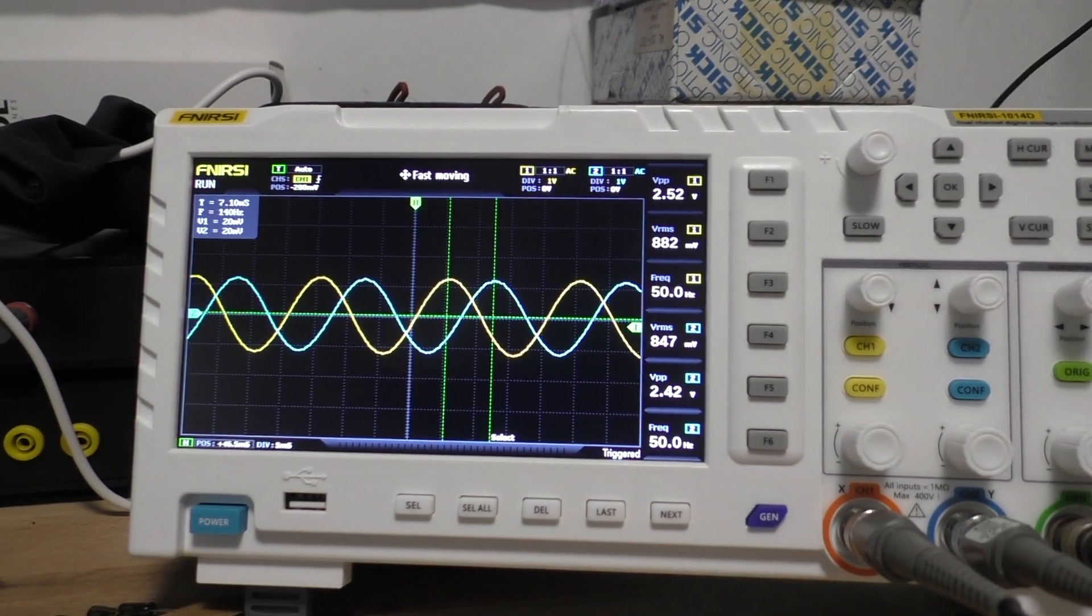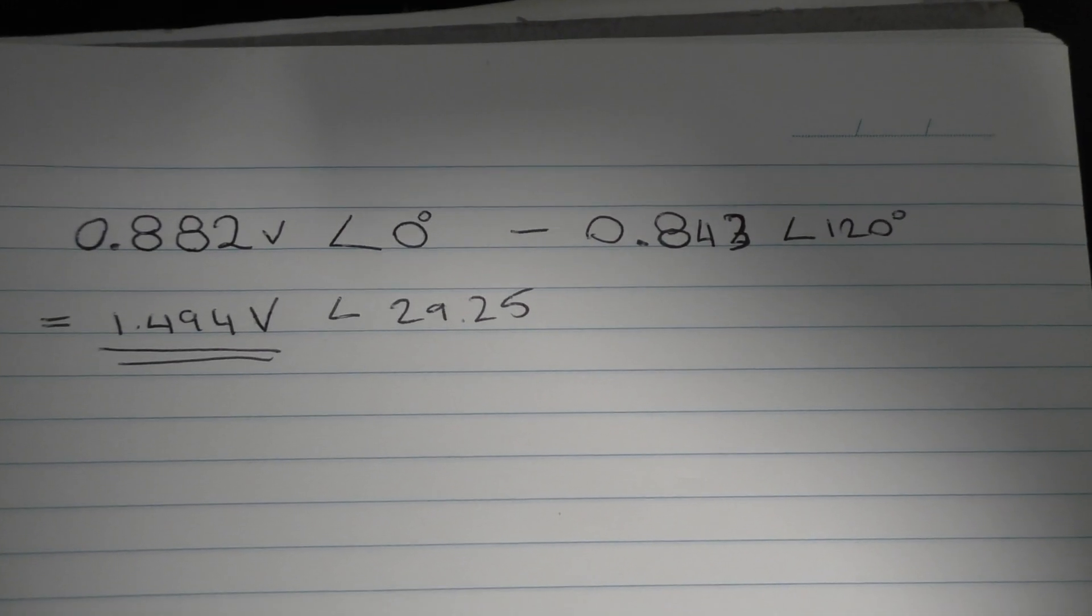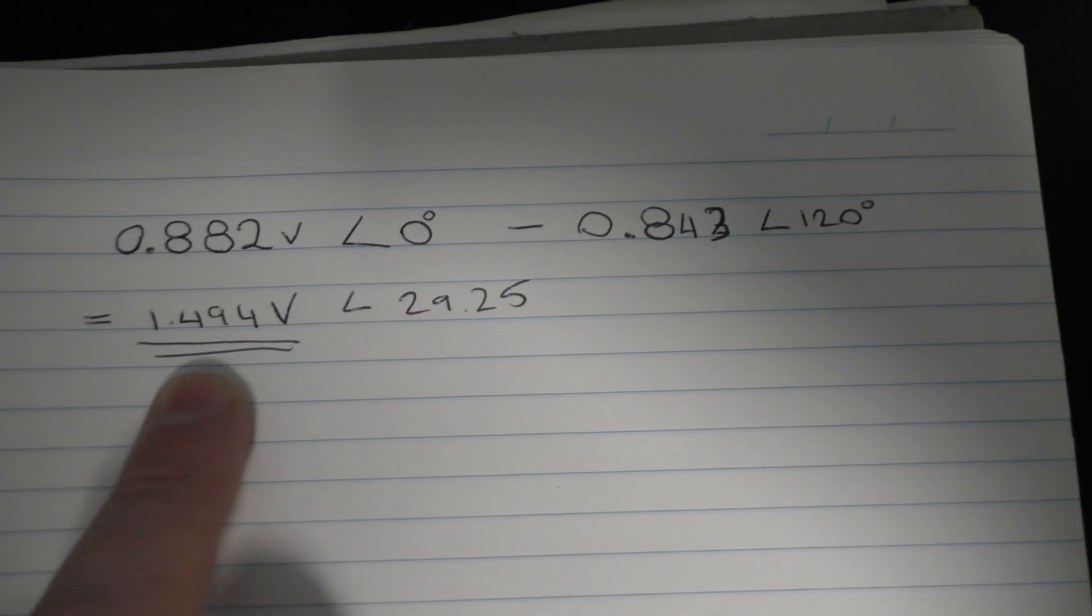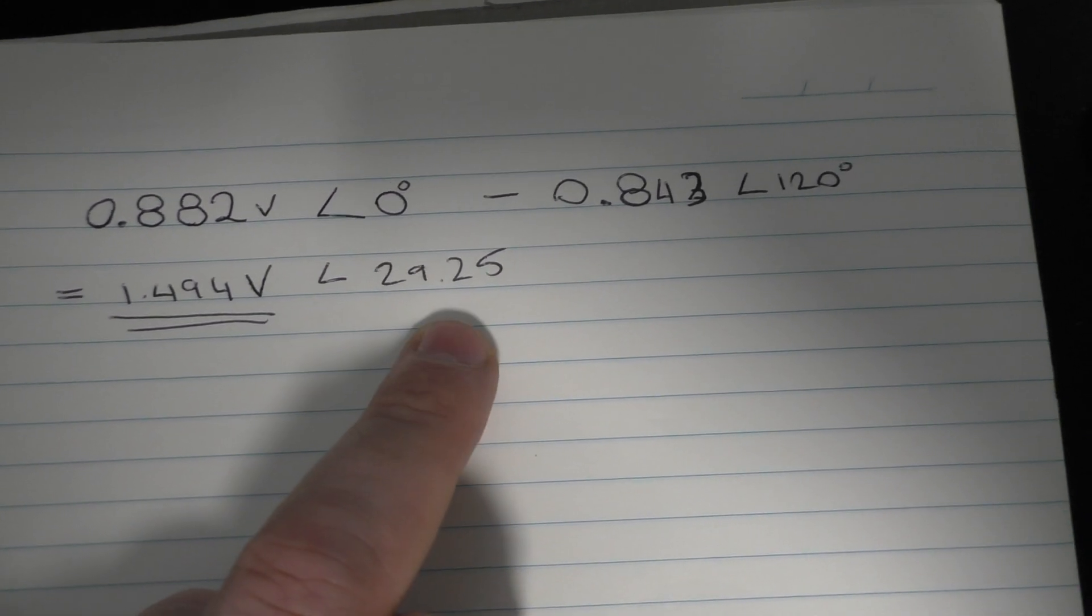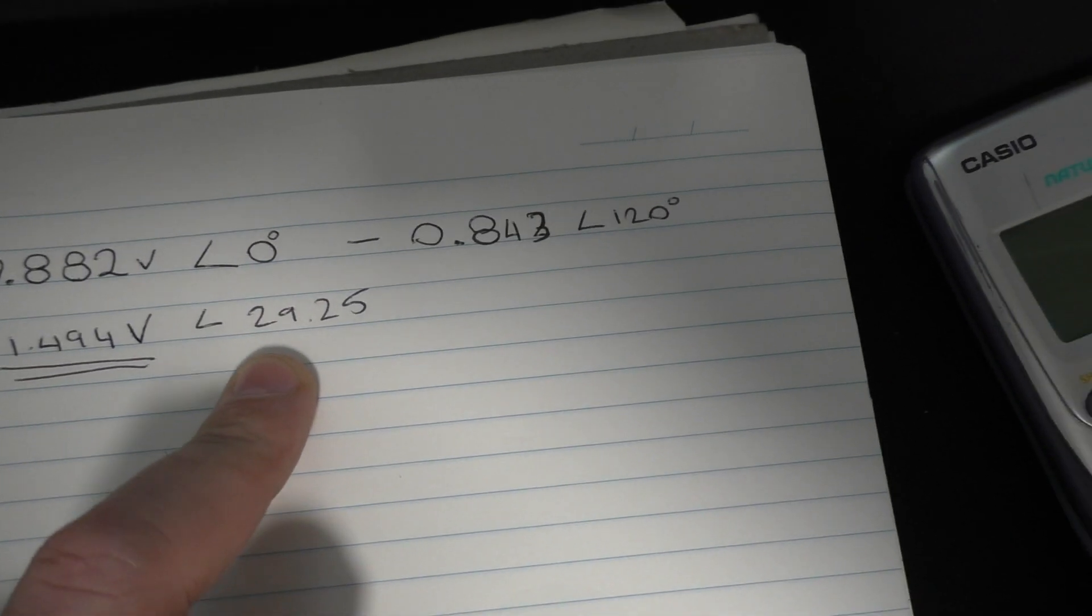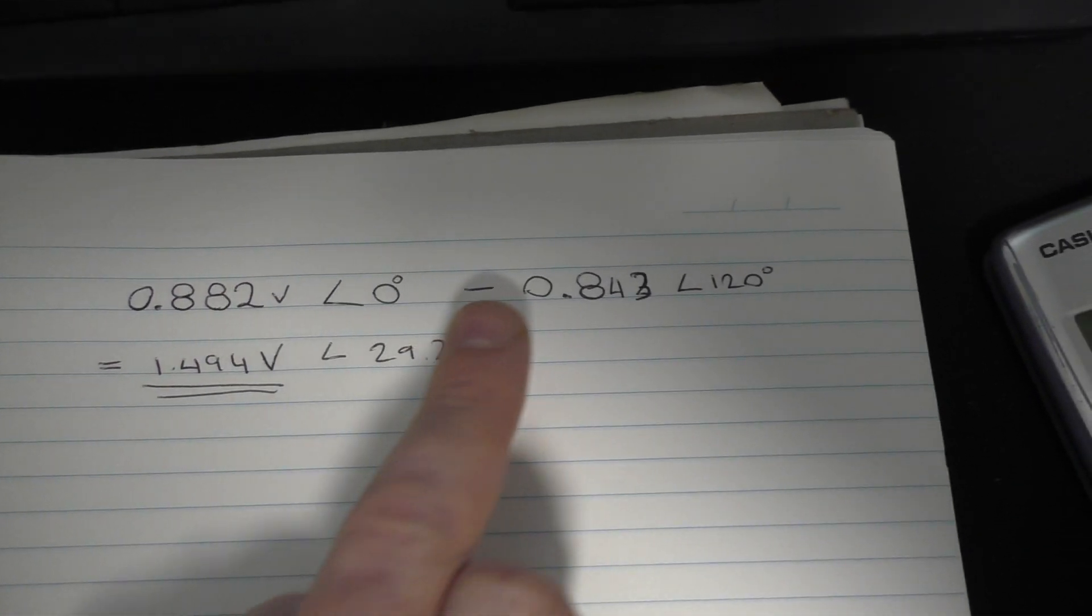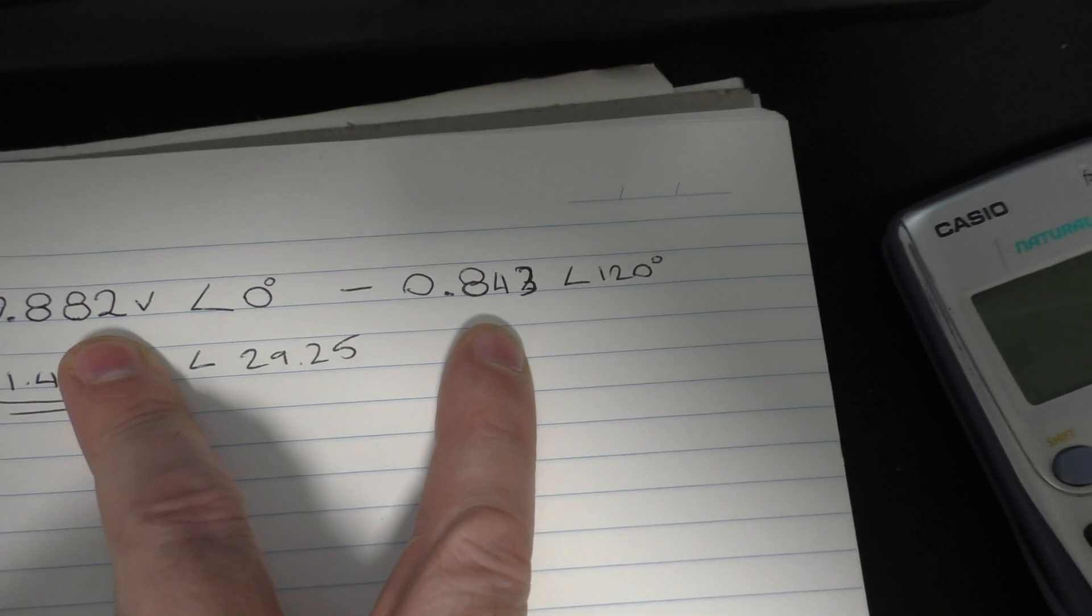So I'm looking at the voltage between there and there, and I've done the math. Between the two, I've got 1.494 volts at 29.25 degrees. Now in a three-phase system that would be 30 degrees, but it's not 30 because of my magnitude error—my magnitude difference, you should say—between the two voltages.